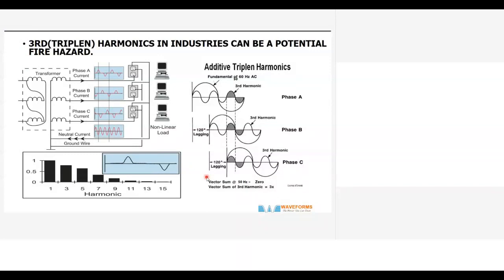So if you see this diagram, you see these 3rd harmonic pulses. They all add up to the neutral. So the neutral current increases, and it circulates in the delta of the distribution transformer. The 3rd harmonic's magnitude is more. It can cause a lot of heating because there is not enough path or grounding wire, so they circulate inside the delta of the transformer.